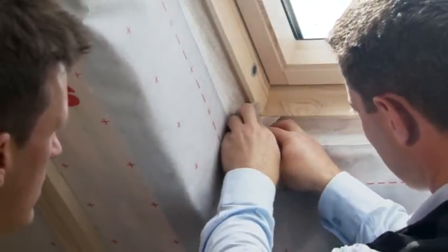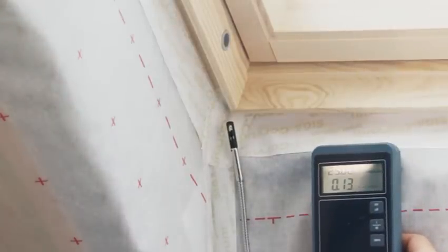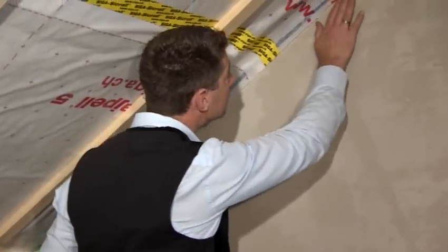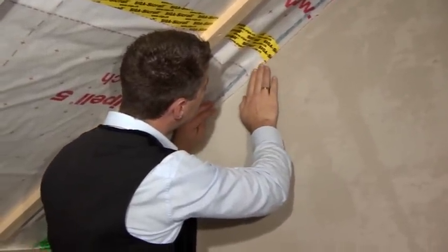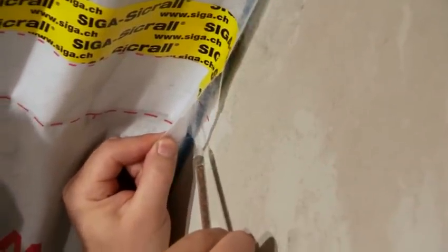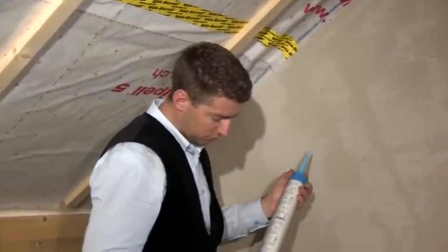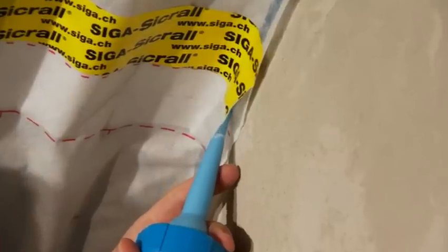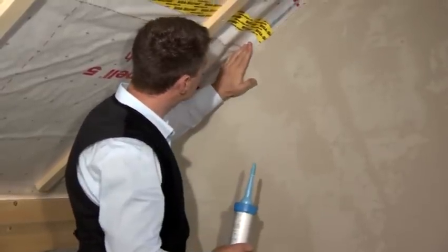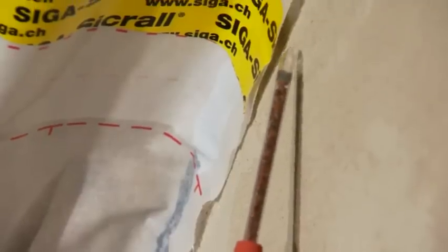The leak is quickly fixed with a short piece of SIGA Corvum. The craftsman checks his work again with the thermoanemometer. Air flows are readily detectable by hand. The smoke tube can be used to conduct a simple check of the component connections. A quick blast of smoke is sufficient to observe where it is forced out through any leaks by the positive pressure. Air is escaping at the overlap of the membranes where they are joined to the wall. Wet insulation and wood structures cause expensive building damage. The professional uses SIGA Primur to repair the leak. The smoke proves it — no more air is escaping.